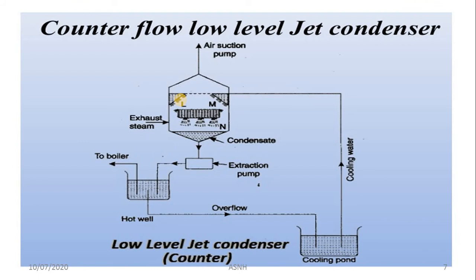The main difference between counter and parallel flow is that in the parallel flow jet condenser, the direction of the steam and the direction of the cooling water entering is the same, but in the counter flow, the direction of the steam entering and the direction of the cooling water entering is totally different.